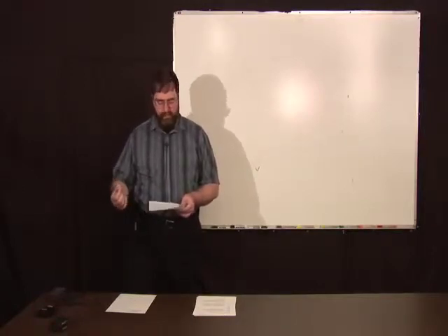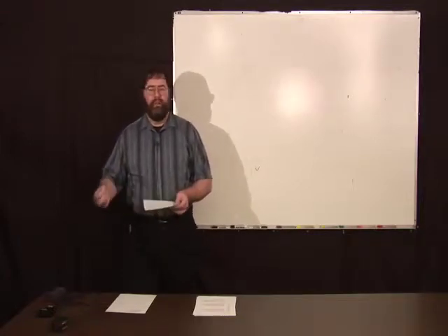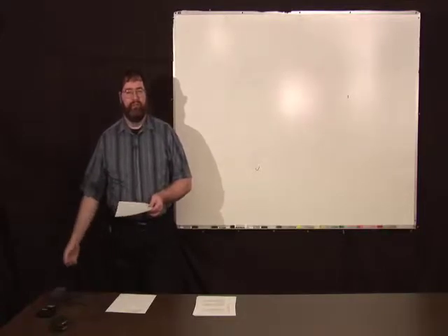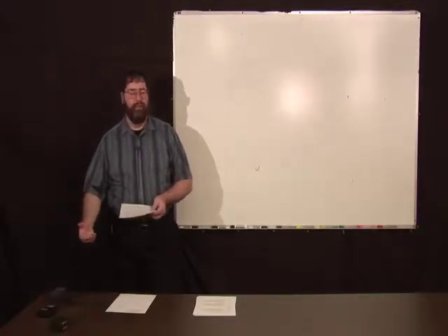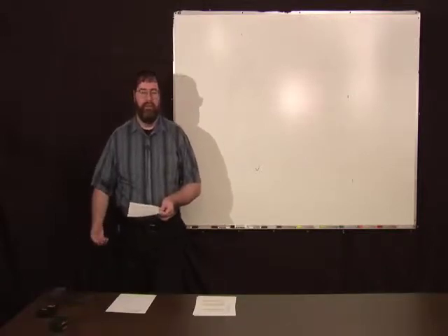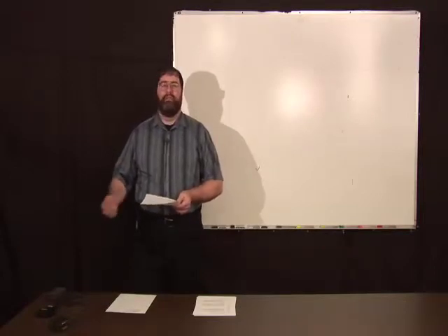So the important thing here is that it is the value of a standard or the result of a measurement that is traceable. Sometimes people say that measurement standards are traceable, or a piece of test equipment is traceable. That's improper terminology. Only the result of a measurement or a value of a standard can be traceable.